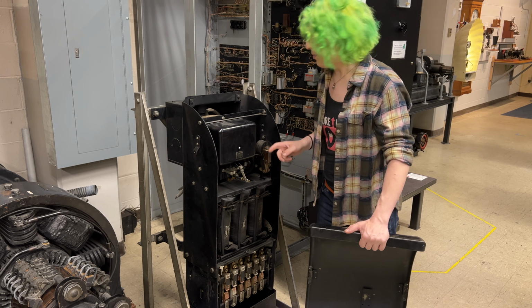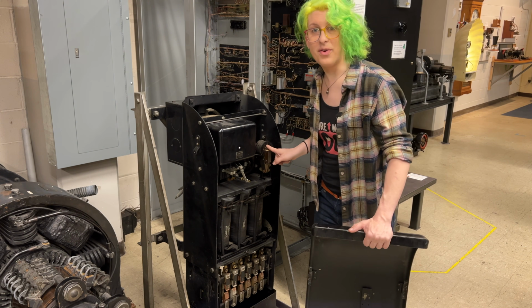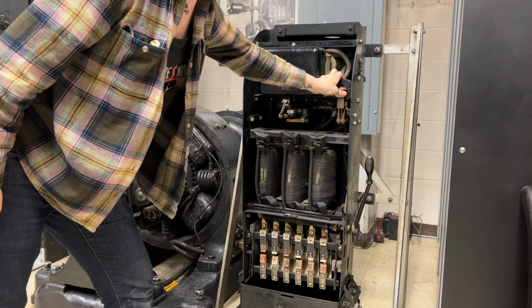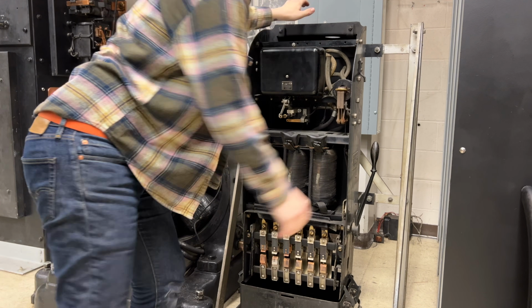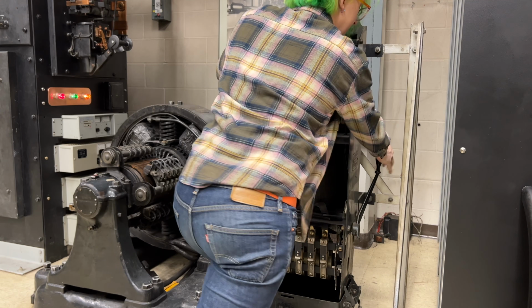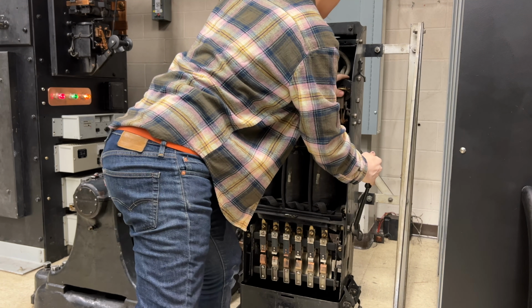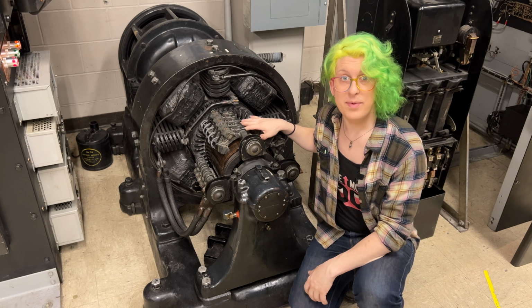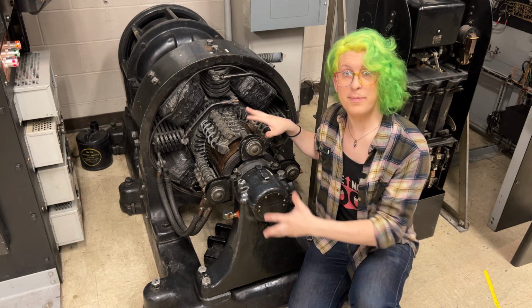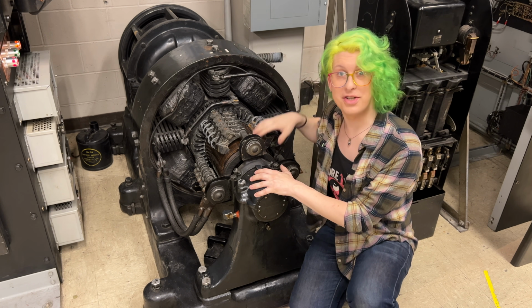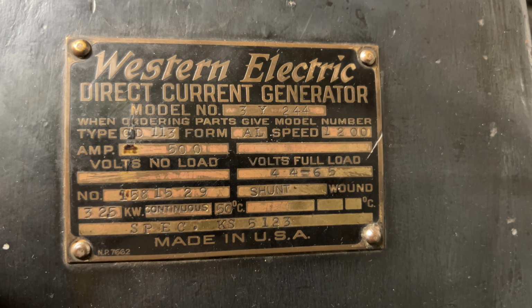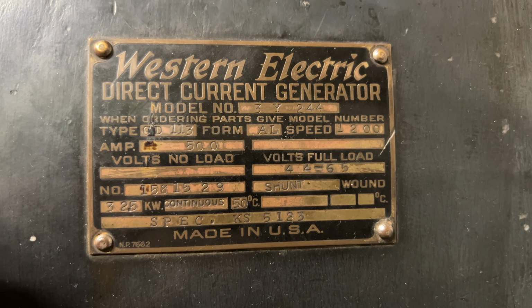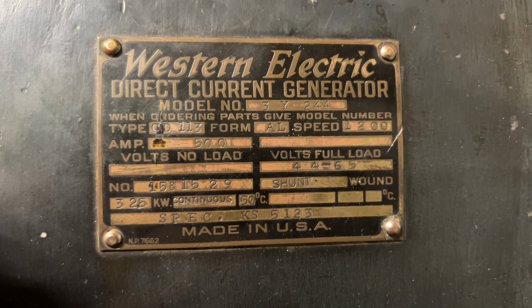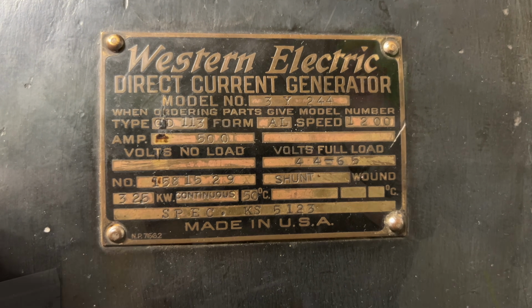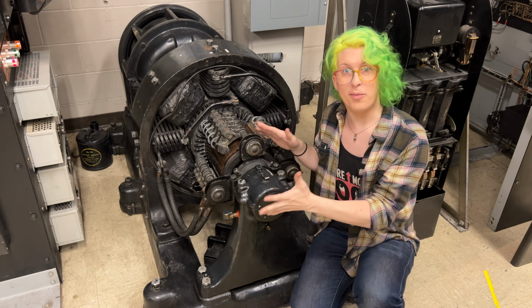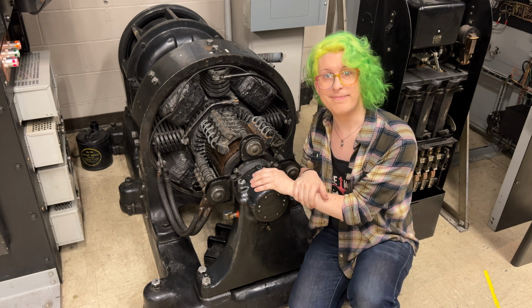The starter lever was locked in position by this solenoid here. If there was an overvoltage or high temperature condition in the AC circuit, the solenoid released and shut down the motor. On this end of the set, we have our DC generator, coupled to the motor by the shaft I mentioned earlier. This particular generator can put out 500 amps at 65 volts, or 32,500 watts, which is quite a bit more than your average laptop charger.